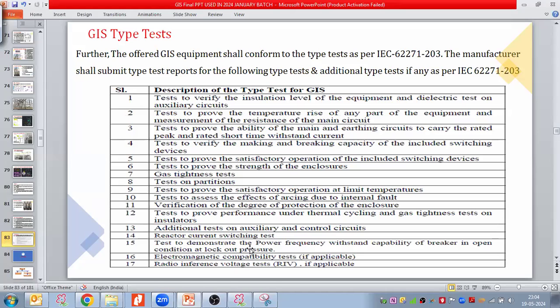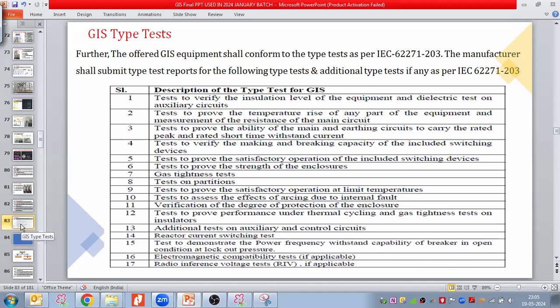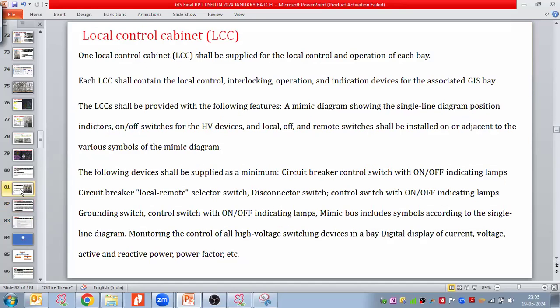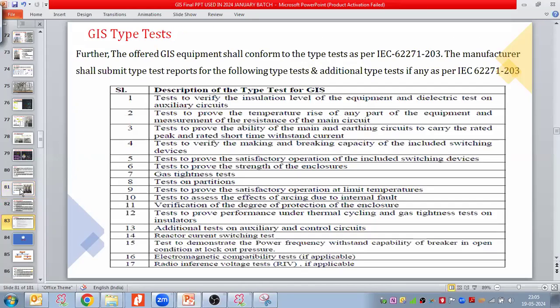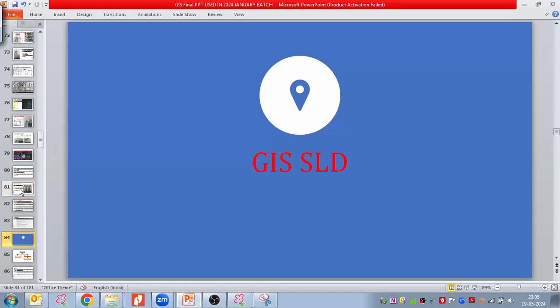In that case, test to demonstrate the power frequency withstand capability of breaker in open conditions at lockout pressure, electromagnetic compatibility test, radio interference test if applicable in the technical specifications. These are tests we ask manufacturer to submit for the review as well at the designing stage, at the approving stage. So now, taking all the discussions, let us enter into the GIS SLD preparations, single line diagram preparations.